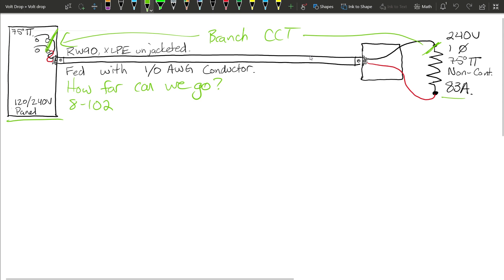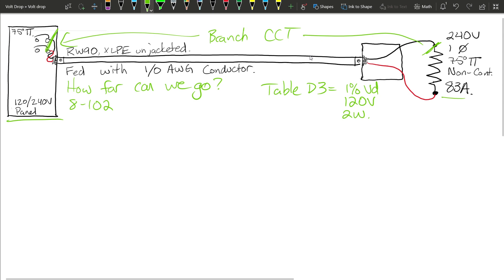A couple of things to remember when dealing with Table D3: it is based off of a 1% volt drop, 120 volts, and a two-wire branch circuit. As we work with larger voltages and larger allowable percent volt drops, it's going to allow us to go further and further. In this example we're going to build our formula based off all of this information — that's how I approach every volt drop calculation.